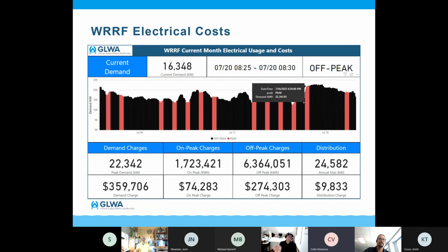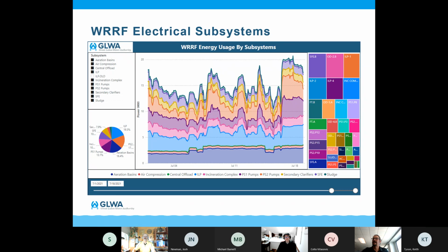On the 15 minutes, it'll look back at the previous 3 15-minute periods, and then it'll be the peak of those 15 minutes. We'll set the 15-minute peak. So that's a cost one.